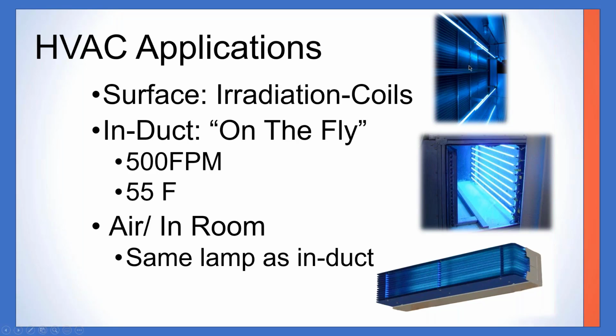So back to the coil, if I'm doing a coil irradiation, again, this is usually used for coil cleanings, drain pan cleaning, and just keeping general maintenance of an air handling system. Well, that's about 7 to 10 watts per square foot. So 7 to 10 lamp watts per square foot. Trying to kill the hardest coronavirus, you're going to have to increase the number of lamps. And to do that, you're going to have to take your intensity up to about 30 plus watts per square foot. Now, what you're seeing in this picture here is an on-the-fly application that's at 500 feet per minute, 55 degrees. This particular one was a government job. I think I might have it on the next slide too, but we'll talk about that one in a minute.